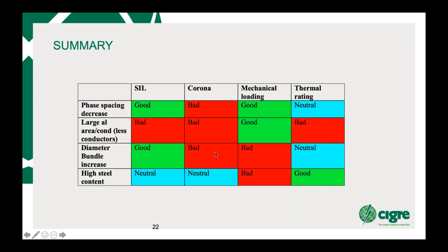The mechanical loading, again, is bad, although the vibration protection is quite good. But the mechanical loading is bad due to the, again, the large bundle management and the wind relating to that, and broken phase considerations. For thermal rating, it's neutral. If you have a high steel content conductor, the SIL is neutral, corona is neutral, mechanical loading is bad due to the high tensile, 10 to UTS, and so you need larger strain towers. Thermal rating is good because you get a lower rate of sag per degree C.